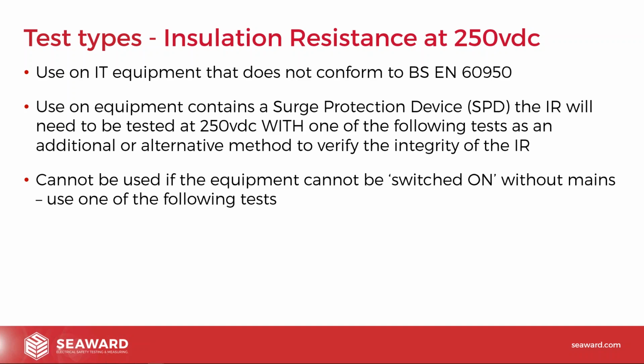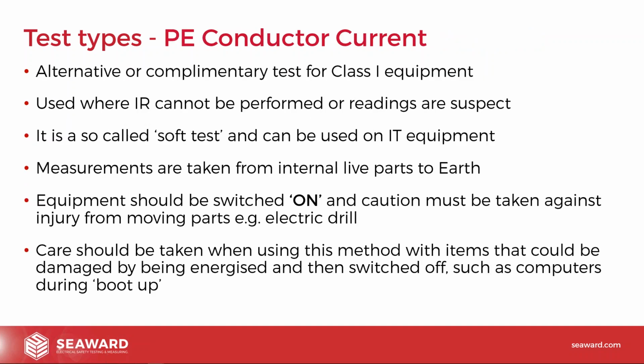It cannot be used if the equipment can't be switched on without the mains use. Again, what we're saying is we should switch the equipment on to carry out the test. So I don't necessarily agree with that one a little bit on there. Really, we should just be able to turn the equipment on and we should be able to do the tests. I think what Paul's getting at there is if you've got equipment with potentially contactors or soft starts, things like that, you can't fully test through the equipment because it doesn't turn on at that point. But realistically, we want to try and turn equipment on. If we can't turn the equipment on, then obviously we can do a 250 or 500 volt test to check up to the switch, but then we'd probably want to do one of the other tests like a leakage test to actually fully test the equipment as well.